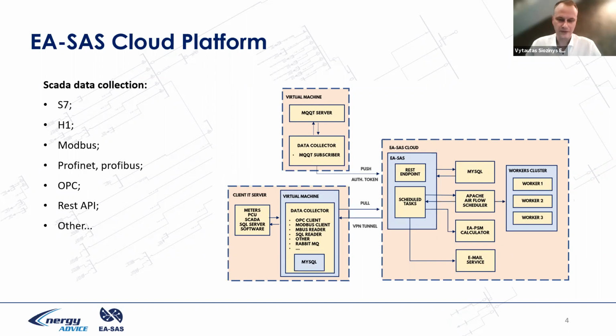So we collect data from the microcontrollers through Modbus, H1, S7, Profinet, or whatever protocols, use OPC servers, and send data to the cloud through the REST API protocol. It is Energy Advice created data collection software, which is installed at the client side in virtual machines, collects data from the meters, SCADA and SQL databases, and delivers it through REST API to the cloud solution.